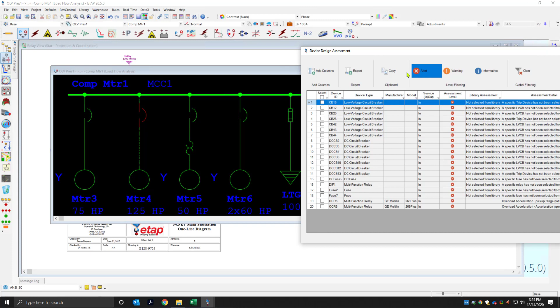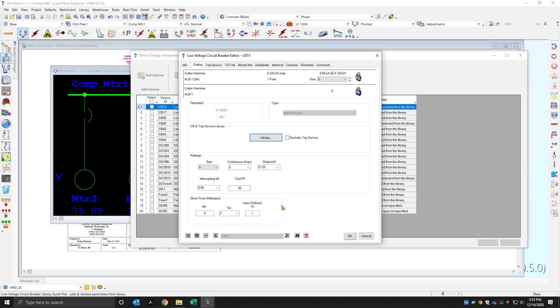So we'll go ahead and click on the alert view, look at circuit breaker 15, which is not selected from the library. You can simply click on CB15 once and the program will take you to that device, or you can double click on that device, open up the editor, and you can see that there is no trip unit specified here, in which case you can simply go ahead and switch to a device that actually has a trip unit. Click OK, and the program reassesses that device and takes it out of your assessment list.